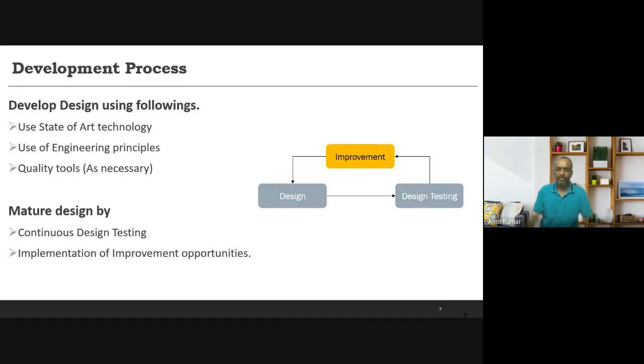So let's say my design boundary is x by x, and I know from all my testing that the product is going to fail at 2x by 2x. So it gives a lot of confidence. It improves the reliability. It improves the confidence of the design team on the product. That okay, even if the device is operated outside its intended boundary, it's not going to fail. Now, why is failure critical if it is being operated outside the intended boundary? It's the quality. It defines the quality. It defines the brand name. It defines the confidence of the customer on the product.